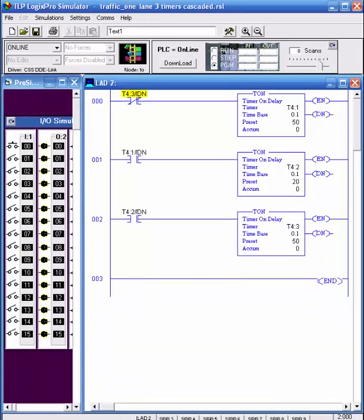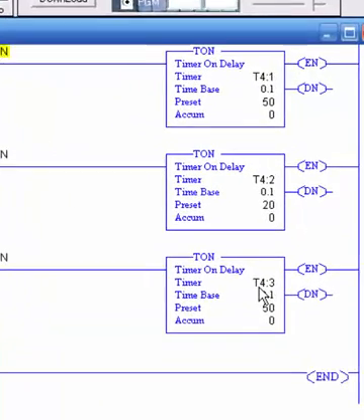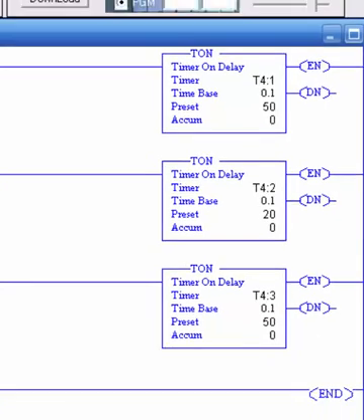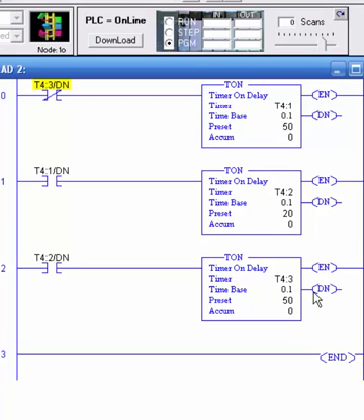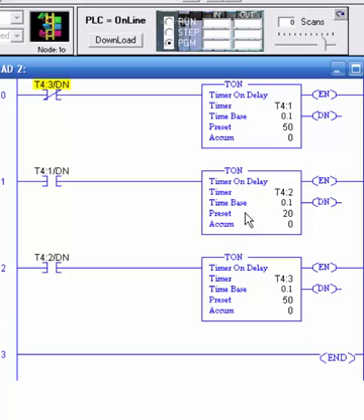As timing gets more complex, here's an application with three timers end-to-end: T4:1, T4:2, and T4:3. The last timer's done bit starts the process. T4:3's done bit is checked with XIO - are you not done? It's not done, so T4:1 counts up for five seconds, then triggers T4:2, which triggers T4:3. When T4:3 is done, it resets everybody, and the cycle starts again. This is called cascading timers - traffic light applications will require lining up several timers like this.